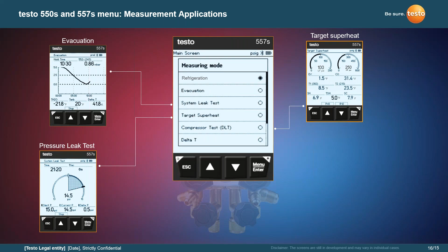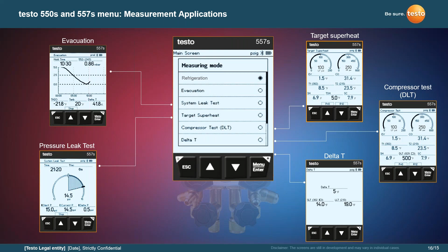You also have targeted superheat, using a psychrometer to get your indoor wet bulb, outdoor dry bulb, and superheat readings with refrigeration side probes and pipe clamps. Compressor test helps you look at the efficiency of your compressor, using multiple pipe clamps. And there's delta T, a different application you can use to perform that measurement.